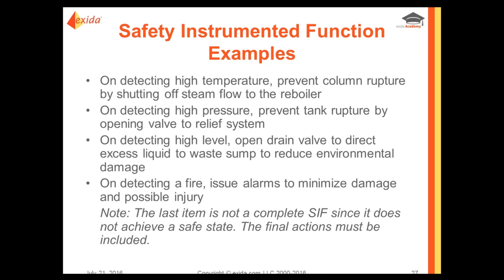Well, not really. The fire alarm we take a look at would not be considered a complete SIF since it does not achieve a safe state. It just issues an alarm to minimize damage. If we want that to be a SIF, you need to include a final action to achieve a safe state, say have a sprinkler system turn on.